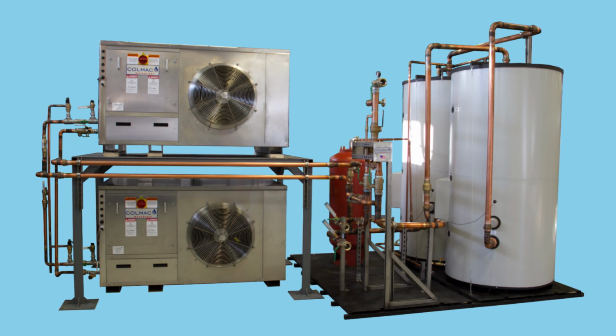Mechanical wax-type valves react too slowly to the temperature swings in these systems. The temperature maintenance system is usually located near the storage tanks, and space must be coordinated with plumbing, electrical, and structural requirements. National Electrical Code also requires 3 feet of clearance in front of swing tanks. In some configurations, a secondary heat exchanger is required between the outdoor compressor and the indoor storage tanks, which means more space and additional drainage must be planned for.